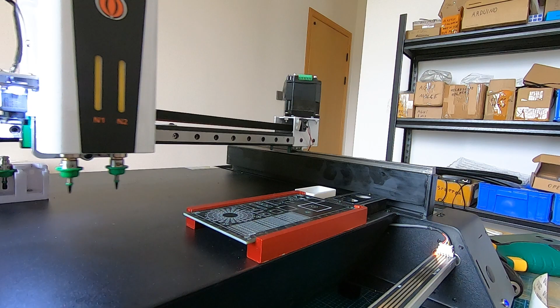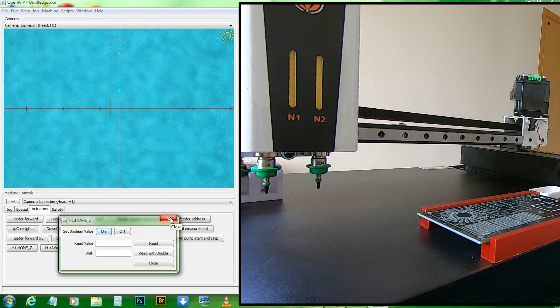Every time a tip is changed automatically, taking it from the tips holder, the Z position is reset with a value stored in the script homez.g. We need to launch a Z reset to check if the value is correct. We can do it by the Actuators tab. Home Z. When I click on, the Z position is reset. Let's check if the Z distance is correct. Let's try with N1.